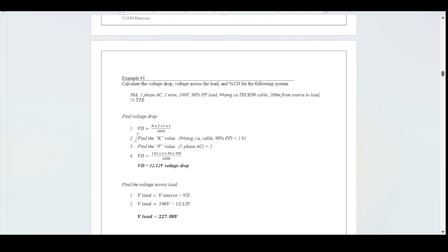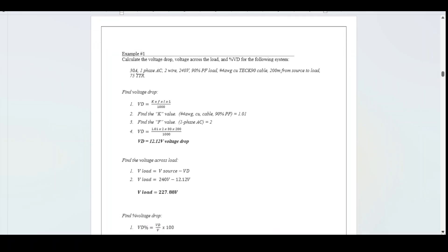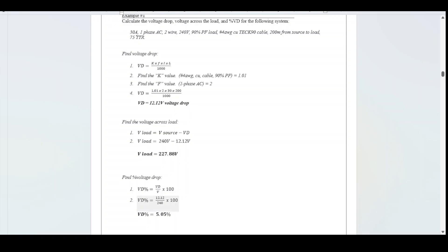First, find the voltage drop using the V_D equation. Using the K-value table: number 4 AWG copper cable at 90% power factor gives a K-value of 1.01. Single-phase AC gives an F-value of 2. Plugging those in gives a voltage drop of 12.12 volts. For voltage across the load: 240 V minus 12.12 V equals 227.88 V. For percent voltage drop: 12.12 divided by 240 times 100 equals 5.05%.